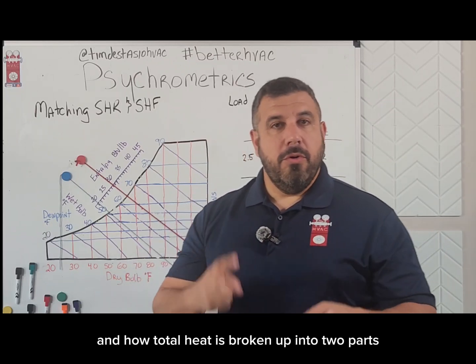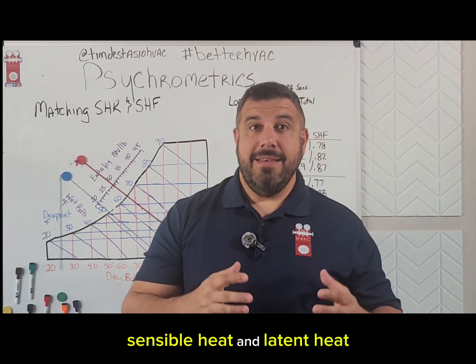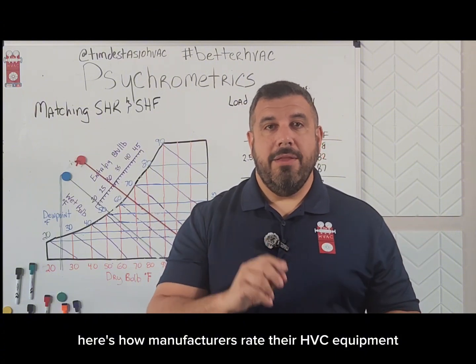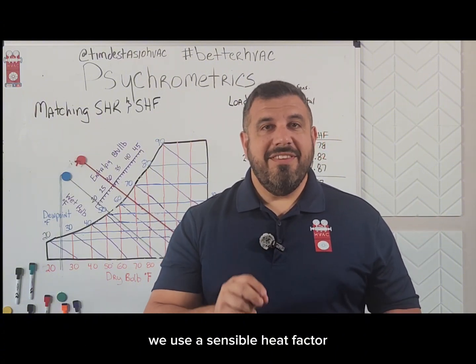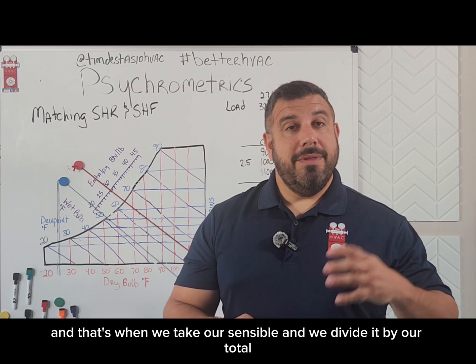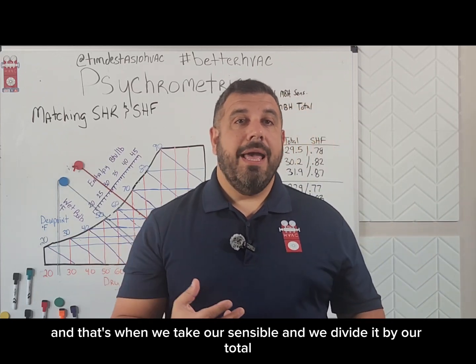We've been talking about enthalpy and total heat, and how total heat is broken up into two parts, sensible heat and latent heat. Here's how manufacturers rate their HVAC equipment. They use a sensible heat factor, and that's when we take our sensible and we divide it by our total.